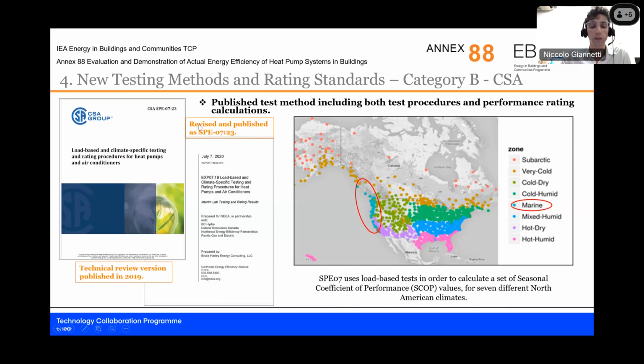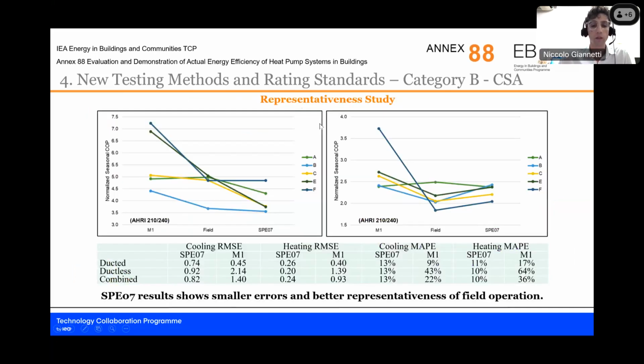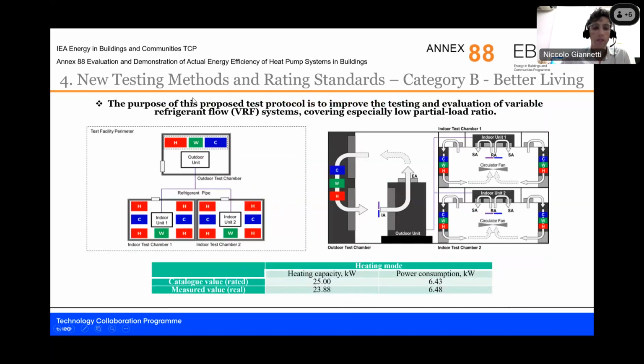That is a published and available standard that can be used for conducting tests, which include both test procedure and also performance rating calculation. In their result, they brought in a very valuable contribution in confirming the representativeness of this testing method, emulator type load-based test. So confirming that the result obtained with this method come closer to those measured in the field when compared to the corresponding unit measured according to AHRI 210/240. Then Better Living and BRI focus on multi-split VRF system. So they address the challenge of having multiple indoor units with unbalanced load, and also confirming result that deviations are obvious with respect to the catalog values.